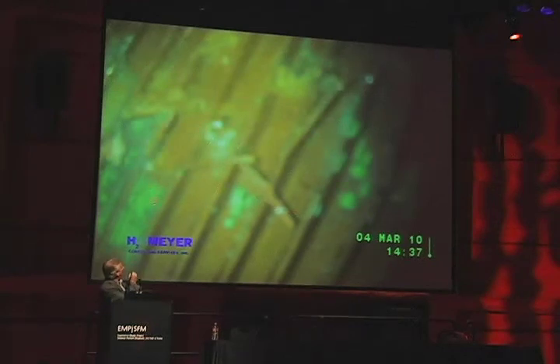I know this picture's fuzzy, but here's an example where you can actually see the enhancements right there. You can see the copper corrosion. In this case, you can also see tube defects. This is where the enhancements have actually split off from the tube itself, so it's actually a tube defect from the manufacturer. We certainly recommend eddy currents and borescoping be done on all new chillers.